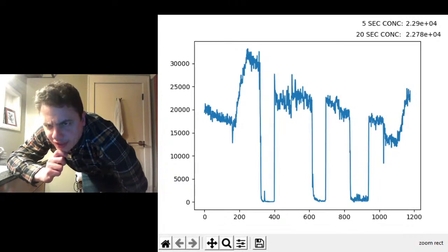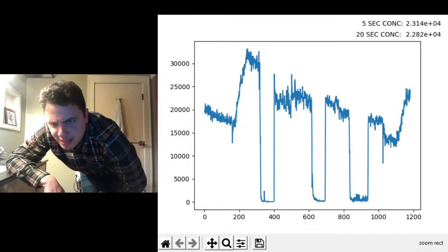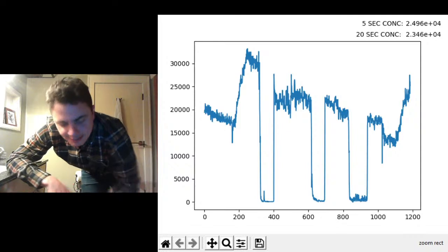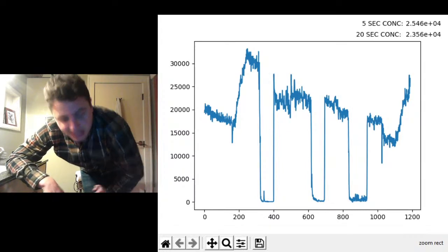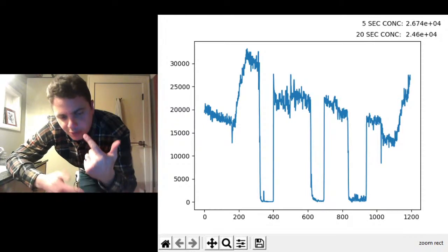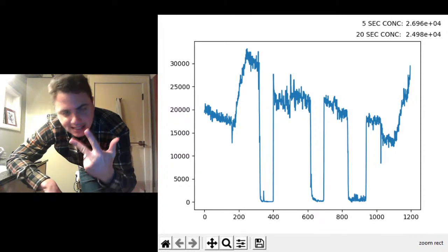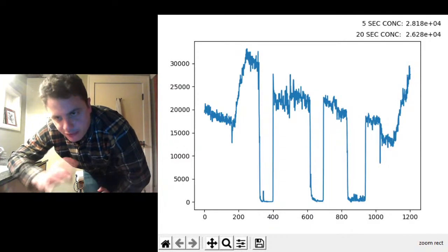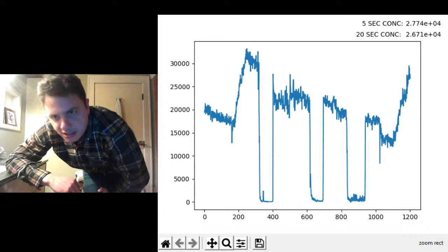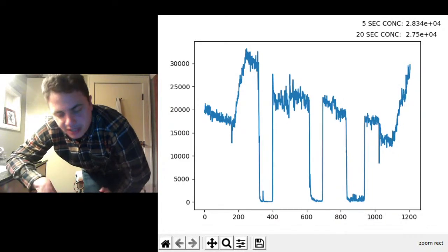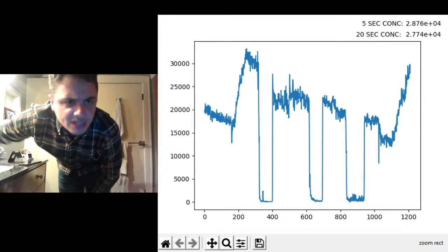Aaron, I feel you agree with aerosol spread being a threat for COVID. What do you think about filtration controls for public settings? HEPA filters, MERV 16? We've got to get ventilation fixed. In the world of engineering controls, it's always limit the source, engineering controls, so that's HVAC with good filters, MERV 13 or higher. And then your last thing is your PPE, so that would be your face mask. So we really should be focusing on ventilation in indoor facilities, HVAC filters like MERV 13 or higher. Getting into the HEPA space would be amazing, but most buildings cannot be retrofit with HEPA, so that's a problem for them.